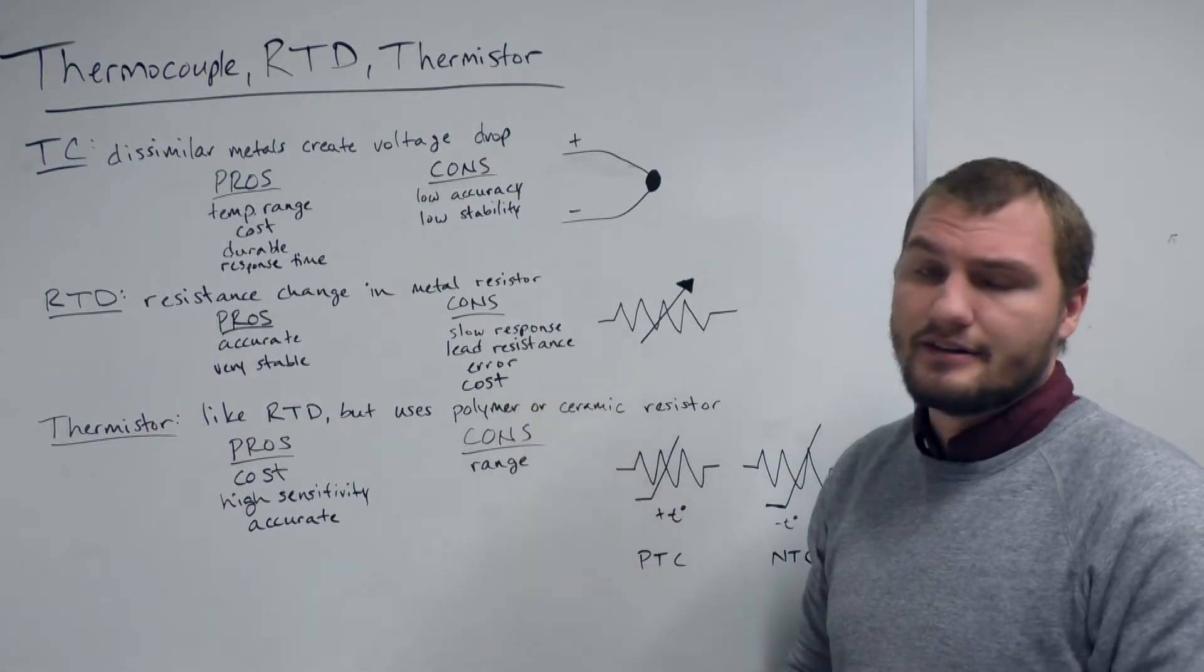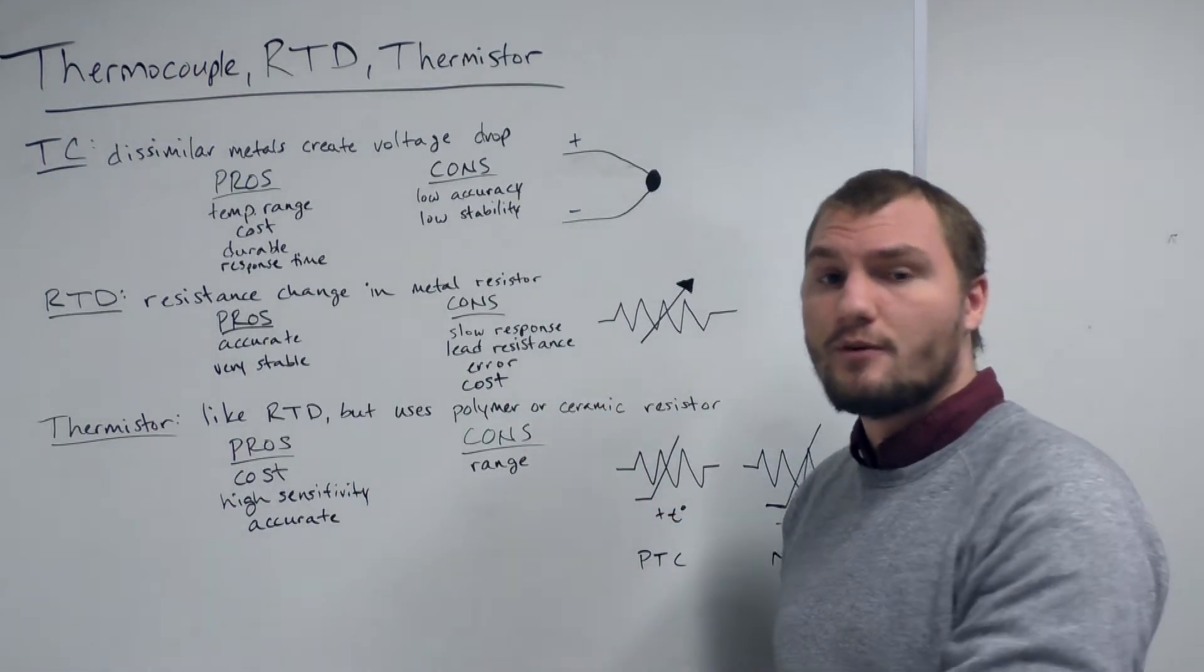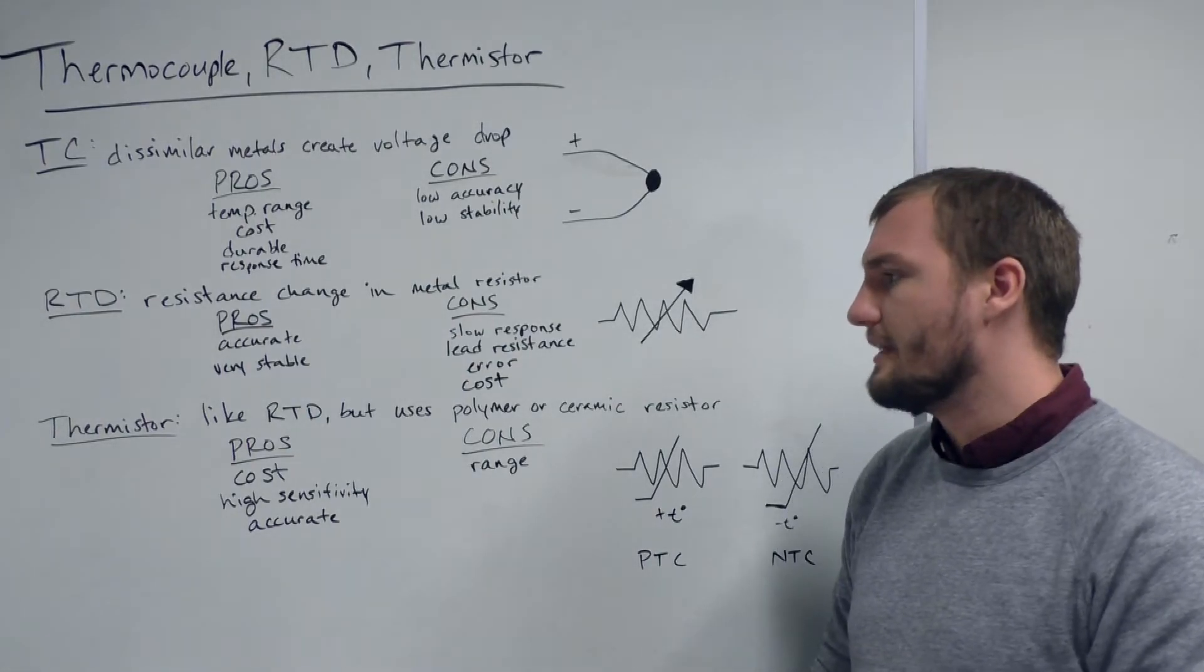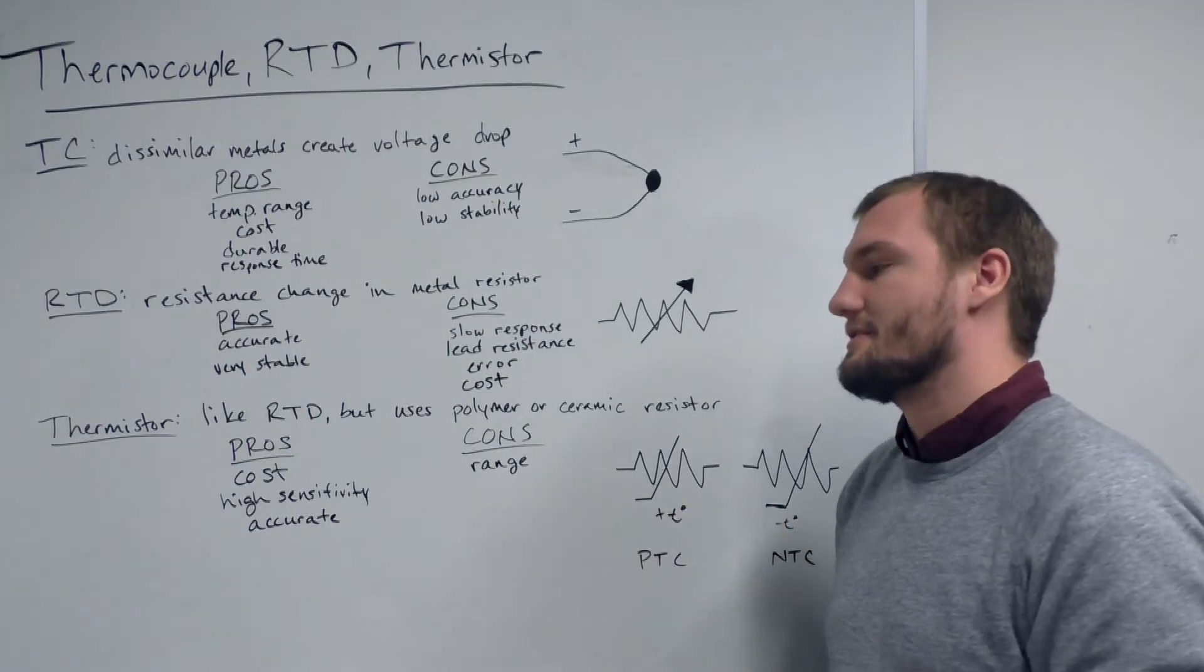Particularly because of this lead resistance error, the two-wire, three-wire, and four-wire RTDs are available to deal with that, and as the wires go up, the price tends to go up as well.